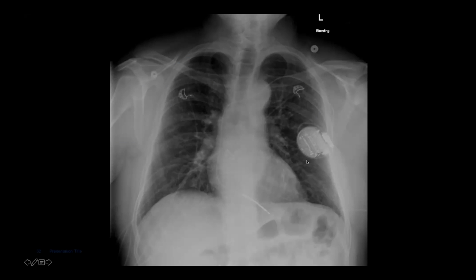So this is what a defibrillator looks like. It looks a lot like a pacemaker. Basically the general system setup is the same. So there's a lead or multiple leads that go down into the heart. But the defibrillator lead, in contrast to the pacemaker lead, has this coil at the end of it. And this is a high voltage coil. And it's through this vector between this high voltage coil and the actual generator that the shock is delivered.